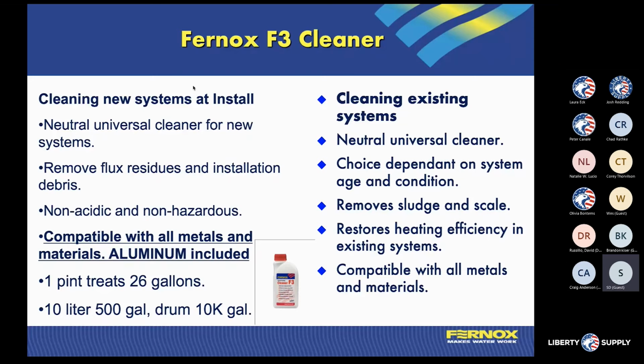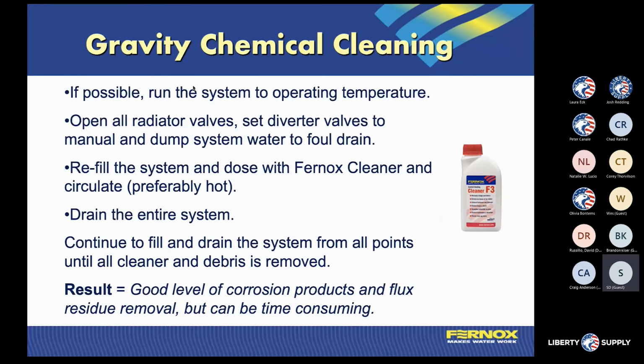The one nice part about all of our system components is you can't overtreat the system. So whether it's the inhibitor or the cleaning product, if you put a little bit too much in, it's not going to affect the system. Our standardized cleaners can stay in solution for about 2 weeks. So if you're going to do a change out or replacement, or you're just going to flush the system down, you can just let it circulate through the system naturally and allow it to scrub the inside of the system, piping, and all the different heat exchangers, and push that into solution. So obviously, if we're doing a gravity style system, which means we're just forcing that chemical through, we're going to let that just circulate through. So that's going to be what we call our natural cleaning process.